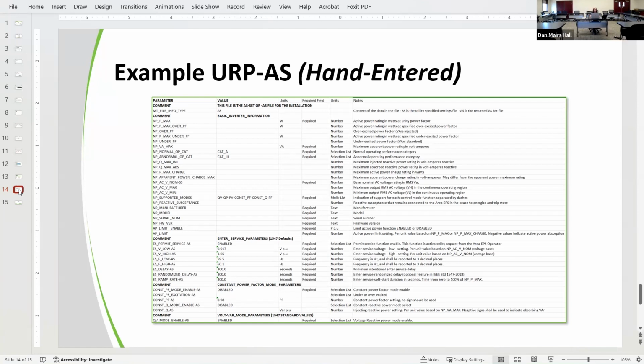It's only at the time of interconnection. So my 2024 technical requirements still apply even if I'm looking at their inverter settings in 2028. I'm not going to ask them to update them. If they add to their system, that's a little bit different of a story, because when you add on to your system, you want the entire system to at least have all the same settings. And we usually would request that they update to the latest and greatest technical requirements at that point in time.